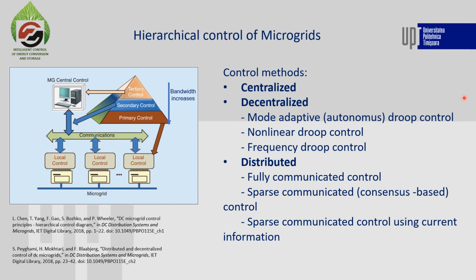Conventionally, droop control is the preferred option at this control level, as it provides autonomous control features to the distributed generators in the presence of communication failures. It effectively deals with the load sharing among distributed generators connected on the same DC bus and provides reference to sub-control loops, which can be voltage or current control loops. Also, the droop control can be perceived as a virtual resistance connected in series with the converter on the DC bus side.